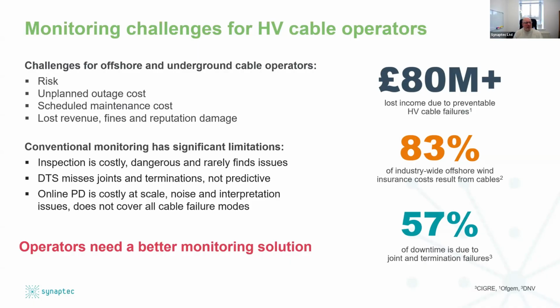What we've discovered is that when people are planning to use cables, the conventional approach to risk analysis and mitigation is to consider things like DTS or online, not offline, but online partial discharge monitoring. Now, when that's done, there are still some risks left unmitigated, and fundamentally, what it boils down to is that the cables themselves, the structural integrity of the XLPE of the cables is actually normally okay. Maybe 30% of failures would be about right. 30 to 40% of failures are in the cables themselves.